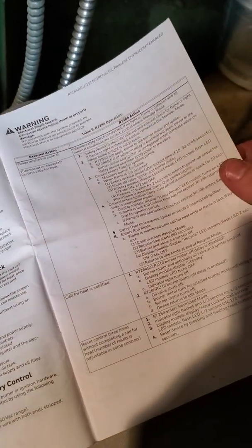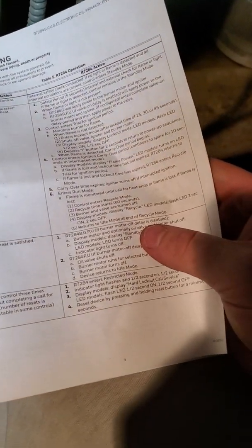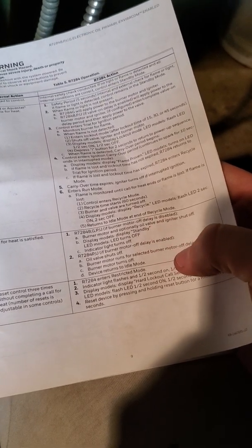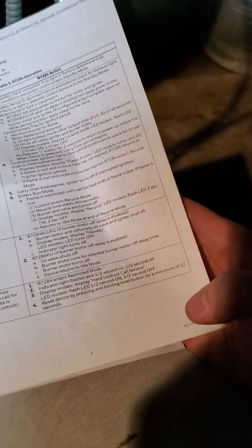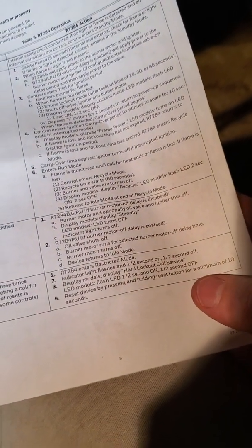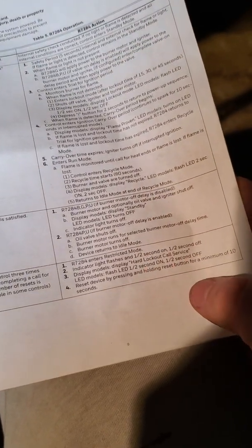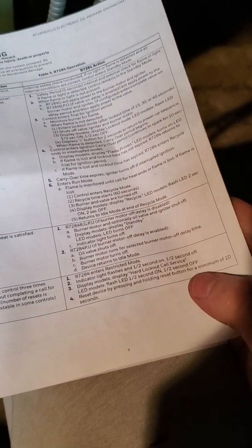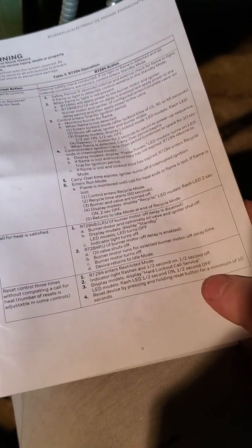Yeah, if you don't have this manual, check it out. Reset control three times without completing a call for heat - number of resets is adjustable in some controls. Reset device by pressing and holding the reset button for a minimum of 10 seconds. So that should get you out - because it enters the restricted mode, hard lockout call service. That should at least help you out.